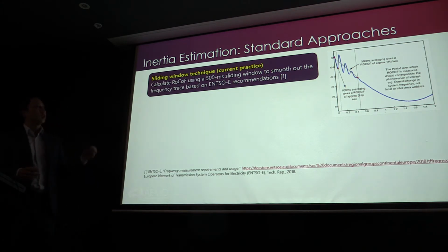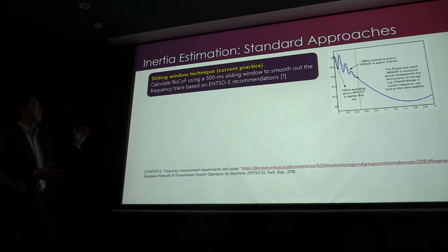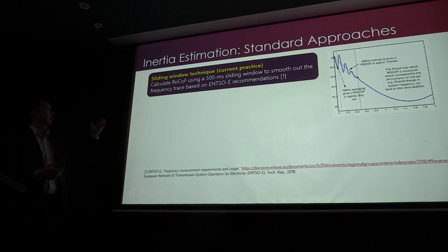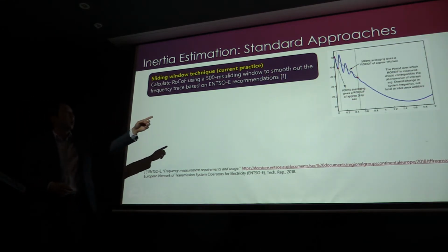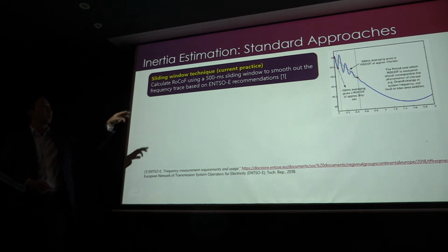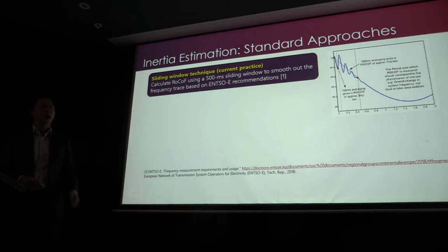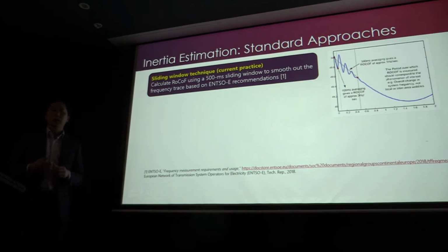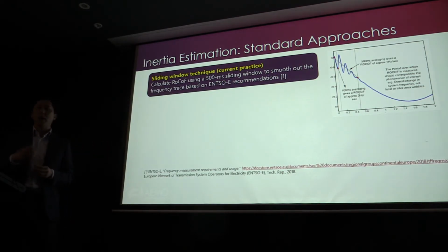So the basic thing is that you need to do some kind of smoothing on the frequency signal before you can work out a RoCoF. There are two really standard practices. First of all is to use a sliding window. Our standard current practice is to use a 500 millisecond sliding window to smooth out the frequency trace. You can see in the picture on the right that you have some oscillations in the frequency trace. If you were to choose a very small window, you'd get a higher RoCoF than was actually there due to the oscillations. Then you choose a 500 millisecond window, and you smooth that a little bit. 500 milliseconds was actually a recommendation from the European grid. We'll probably talk about this a bit later, about why that may or may not be good for the SWIS.